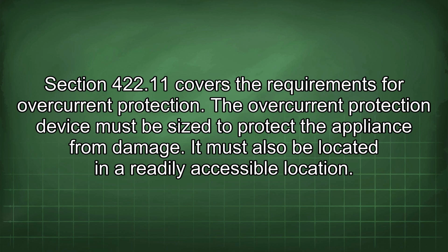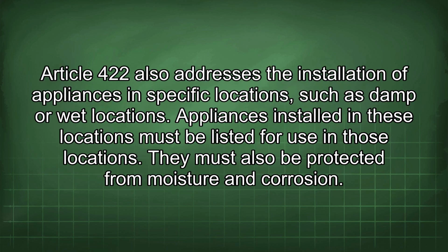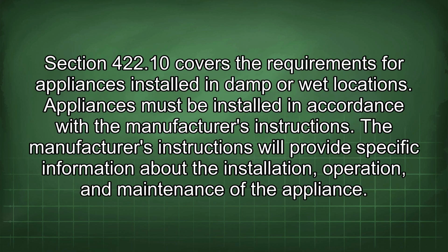The overcurrent protection device must be sized to protect the appliance from damage. It must also be located in a readily accessible location. Article 422 also addresses the installation of appliances in specific locations, such as damp or wet locations. Appliances installed in these locations must be listed for use in those locations. They must also be protected from moisture and corrosion. Section 422.10 covers the requirements for appliances installed in damp or wet locations.